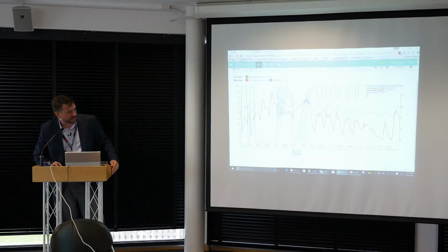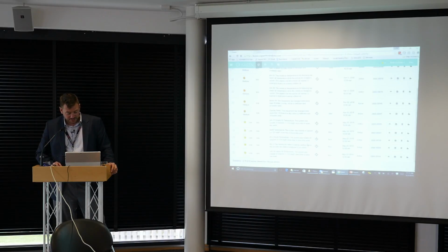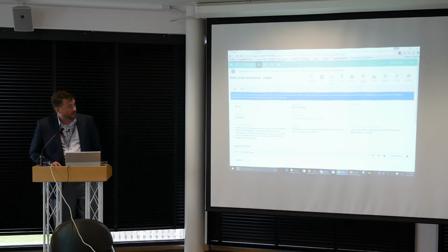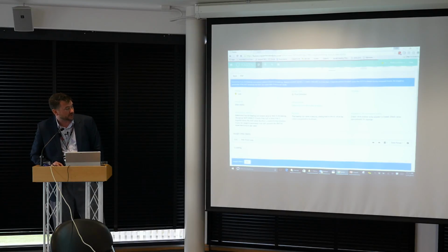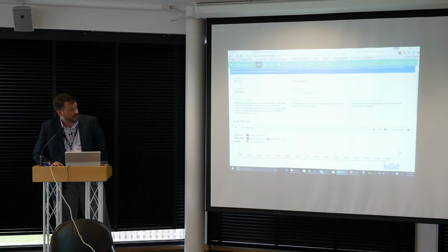Let's look at my damper position here. What's my delta T here between these two? Oh, I do have a problem, or maybe I don't have a problem. So let's go look and see a couple of fault detection diagnostics. So the heating coil is leaking, adding heat to the air while the valve is supposed to be closed. Let's look at that. On my air handler, it's determined this based on the National Institute of Standards and Technology, NIST APAR rules. So if somebody out in the industry, they've got industry standard rules for when things are wrong. It's telling me that my supply air temperature is more than 2 degrees above the mixed air temperature when the heating coil valve is closed during occupied hours.